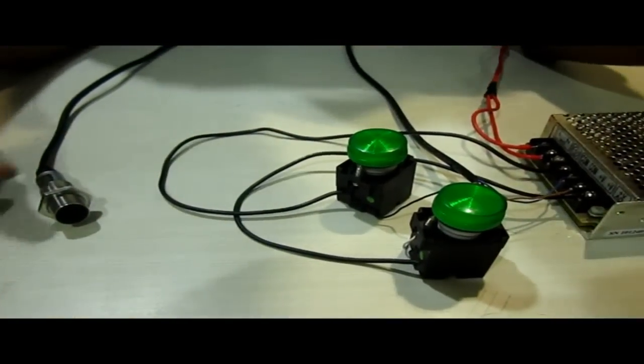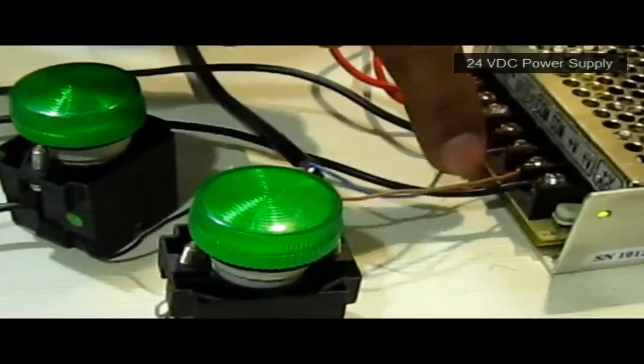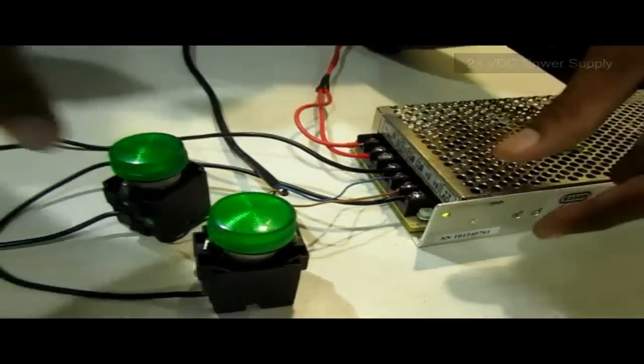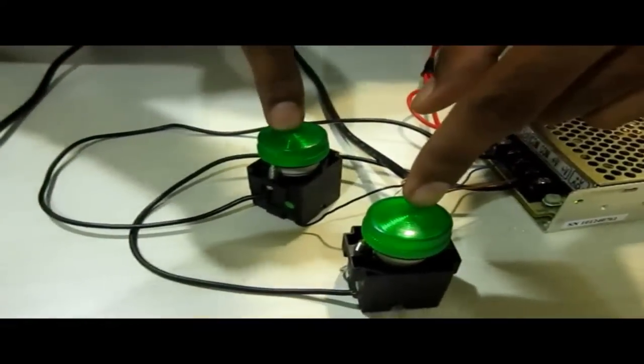Now I have wired up the whole circuit. As you can see here I have connected 24 volt to the brown wire and 0 volt to the blue wire. These are the operating voltages to turn on the sensor. And the output wires are connected to the two respective indicators.